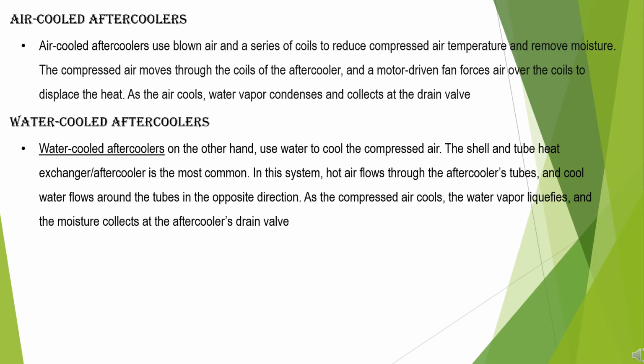Air-cooled aftercoolers. Air-cooled aftercoolers use blown air and a series of coils to reduce compressed air temperature and remove moisture. The compressed air moves through the coil of the aftercooler, and a motor-driven fan forces air over the coil to displace the heat. As the air cools, water vapor condenses and collects at the drain valve.